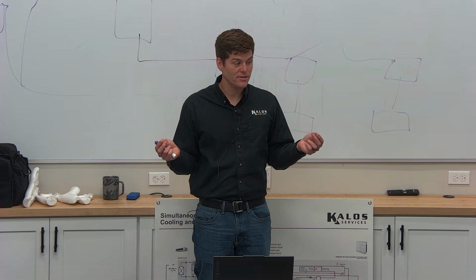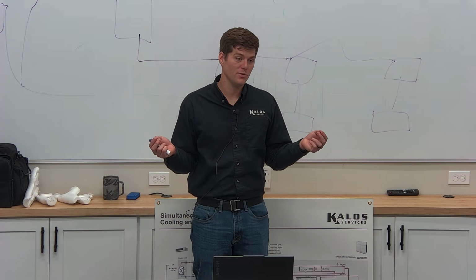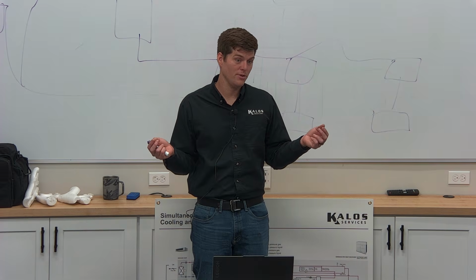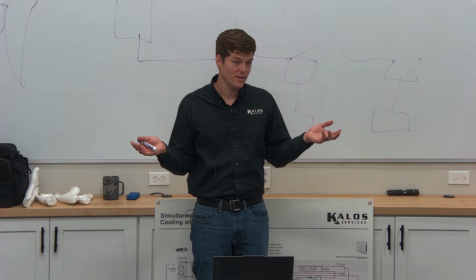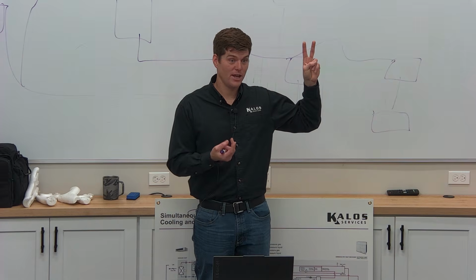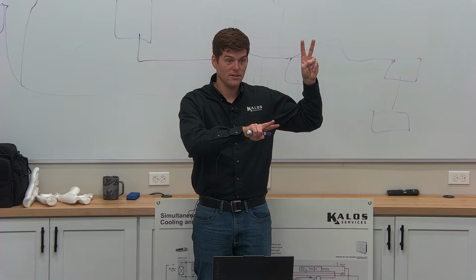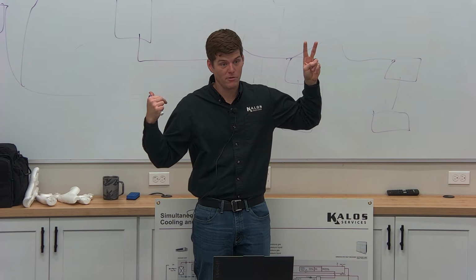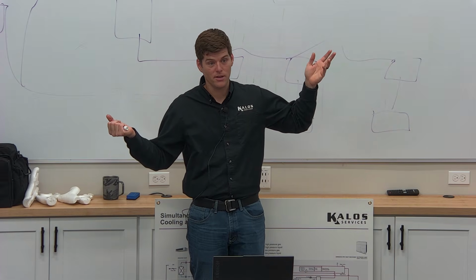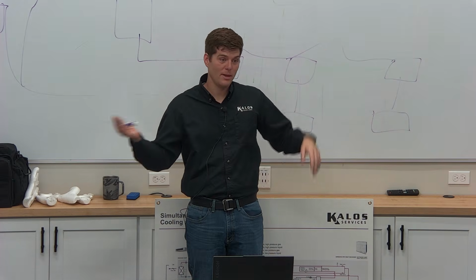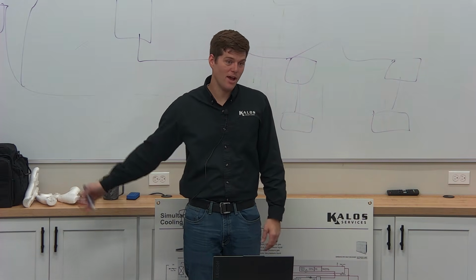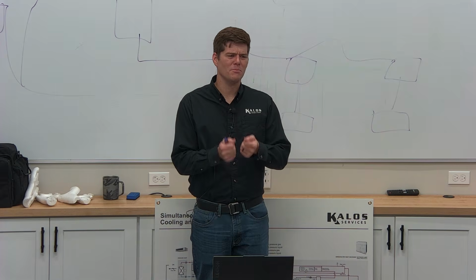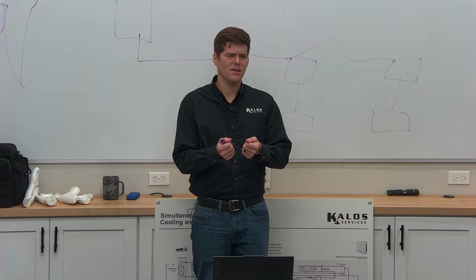And they're non-polarity sensitive. So even if you mess it up and change colors between the indoor unit and outdoor unit, or indoor unit and BS box, it still knows what it's doing and who it's talking to. So I can go red and black, and then on my next unit do black and red by accident, right? Because I had to go out to my truck and grab a wrench, and then my wife called me, and then I came back inside. Oh, I got to use the bathroom now. And then I finally get back to that last one and I'm like, wait, did I do red and black, or black and red? It doesn't matter.